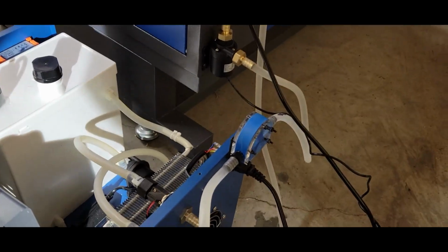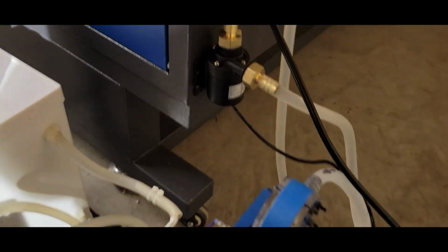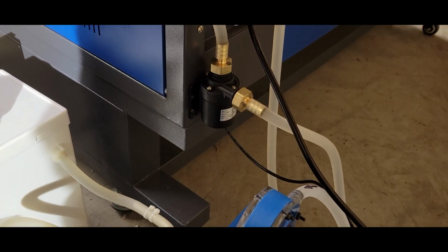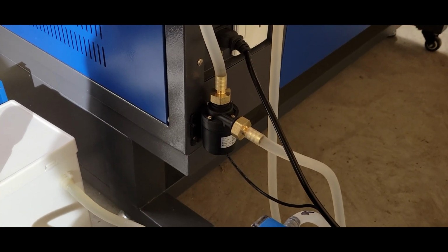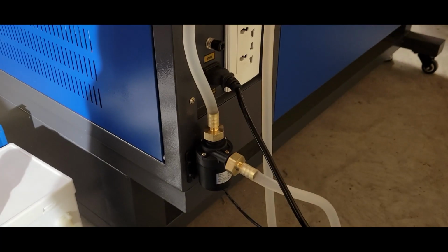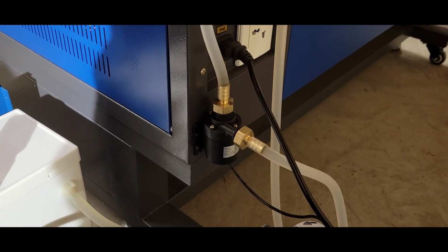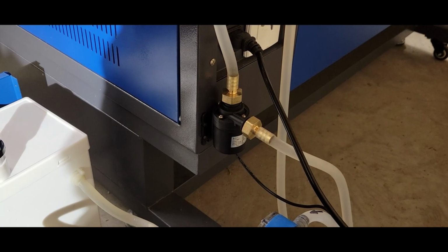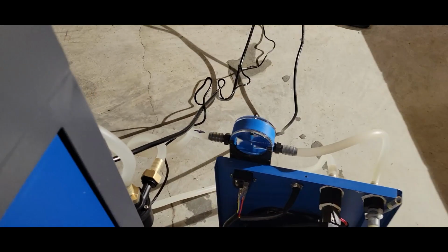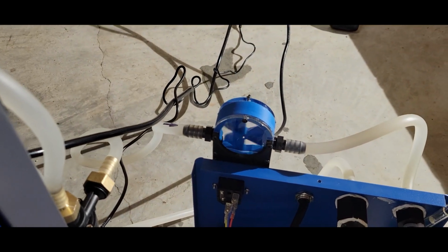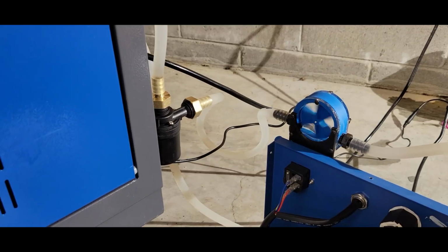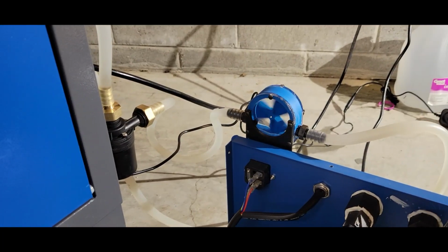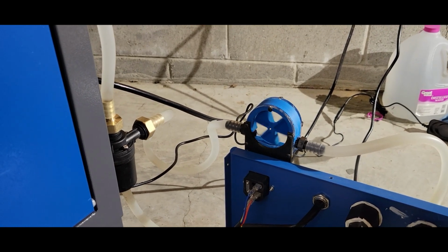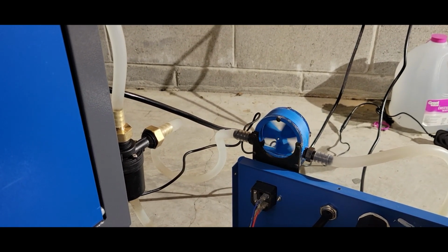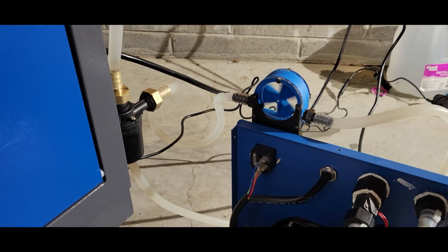One of the other things I think people would like to know, and I've seen on Chad's Custom Creations, people were concerned about having this pump in line with the water lines - will it work if you leave it in place, will the main pump work? Well, right now I'm running the main pump and the water is moving quite well, no problem at all. The pump doesn't have to pump as much as the chiller pump does, but it has to move the water well enough to keep warm water passing through the entire circuit.